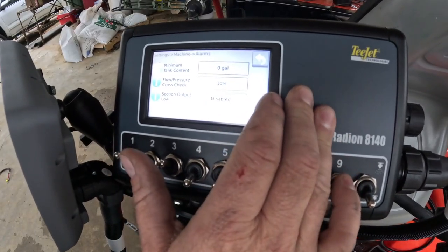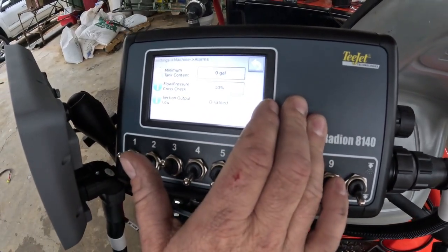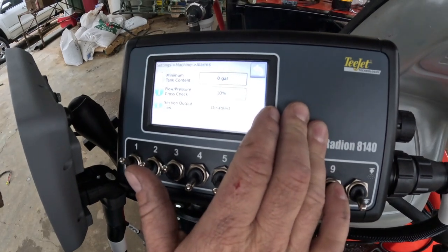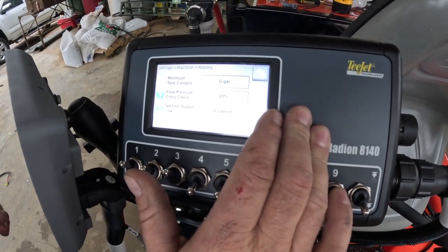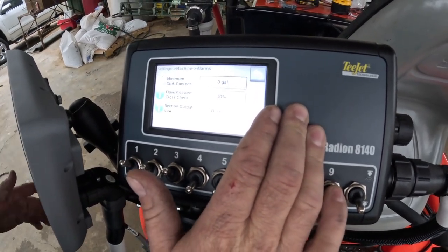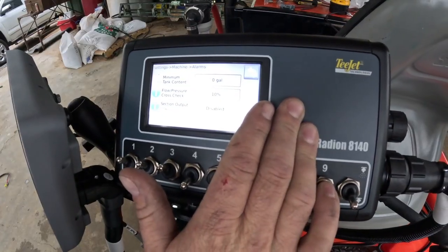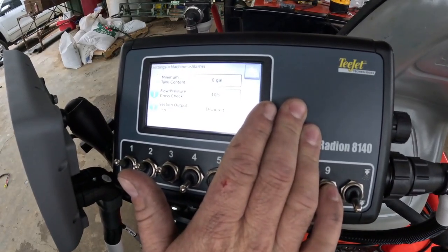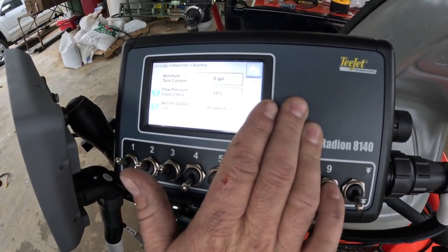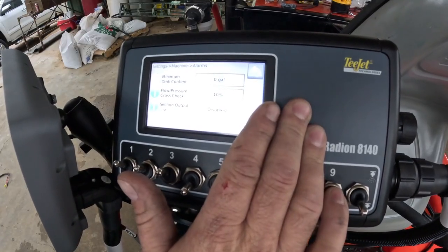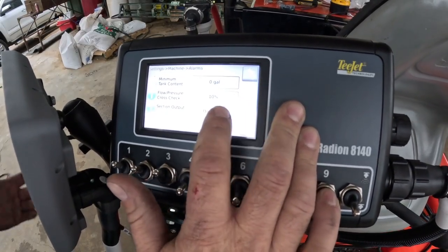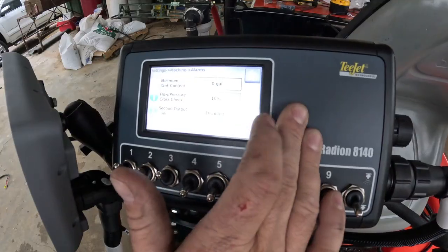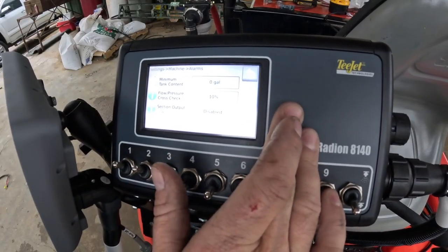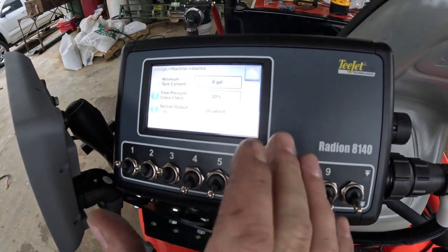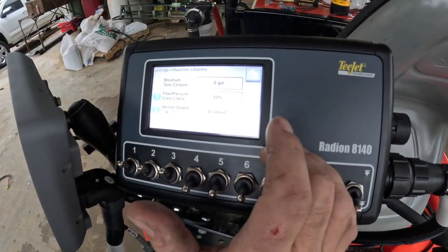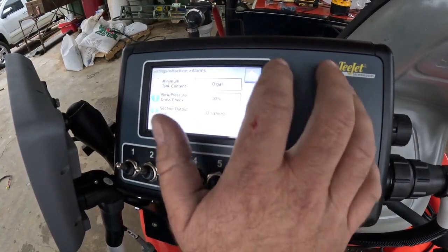Flow pressure cross check. So what that is for: if you've selected a tip in here that's a red tip, an 04 tip, but you're actually running an 05 or an 06 and the system is in flow mode, it's going to see that, hey, the flow we're at is correct, but our pressure is off, and it's going to be off by more than 10% in this case. So it's going to throw an alarm to tell you that something's wrong. And in your scenario, you would need to go back and select the right tip. So making sure the right tip is selected is very important.